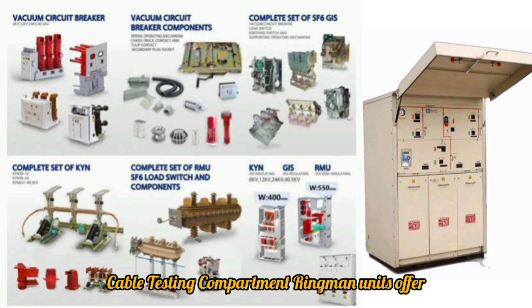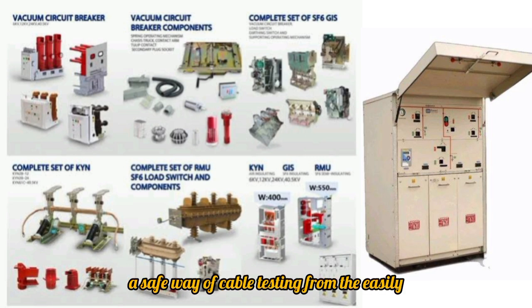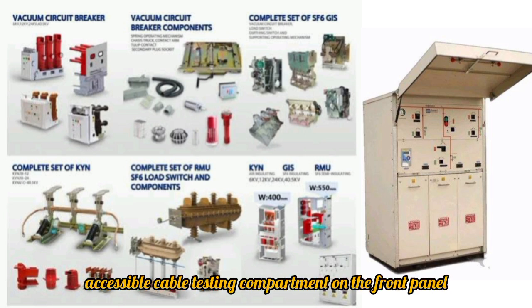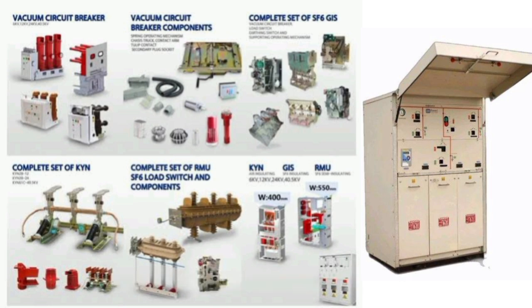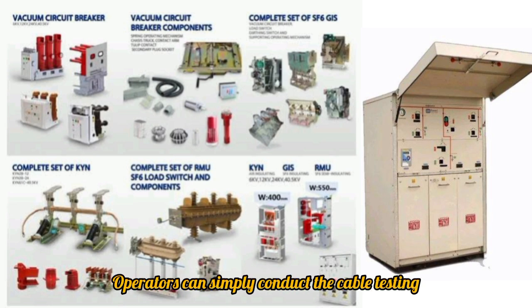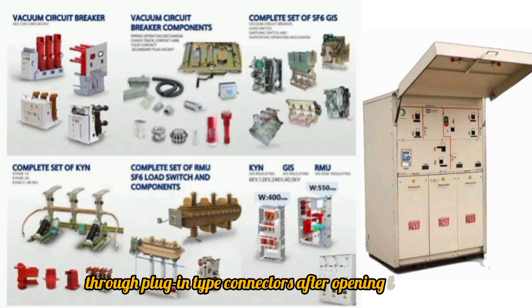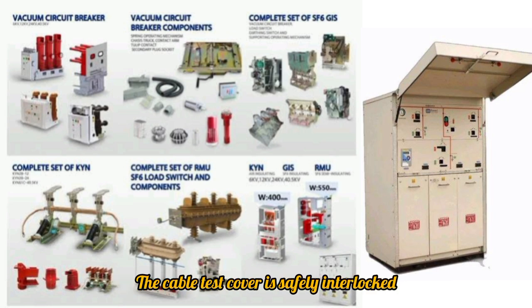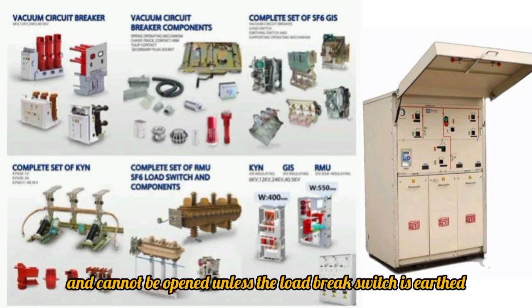Cable testing compartment. Ring main units offer a safe way of cable testing from the easily accessible cable testing compartment on the front panel. Operators can simply conduct the cable testing through plug-in type connectors after opening the cover. The cable test cover is safely interlocked and cannot be opened unless the load break switch is earthed.